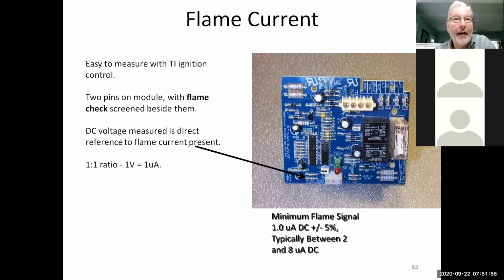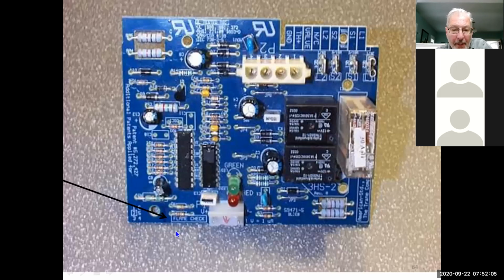For the flame sense on these units, since we don't have a flame sensor, it's on the board. If you look on the board, there's a flame check, and then there's a V plus and a V minus. So if you put your meter on V plus and V minus, it's going to convert microamps to DC volts, and it'll go from 2 to 4 microamps or 2 to 6 microamps, or in other words, 2 to 6 DC volts.